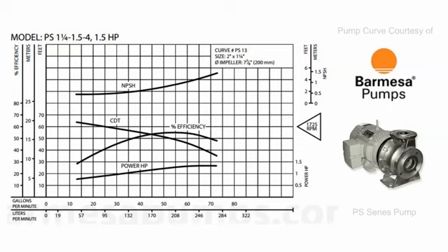That generalization comes along on the basis that you don't always have an efficiency curve available, and it's most often the case that the pump's performance and the efficiency curves are going to intersect more closely towards the middle of the curve, because in most cases a pump is designed around that middle point, and then everything else that occurs is essentially just a byproduct.